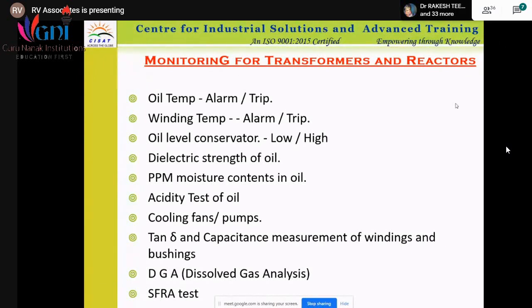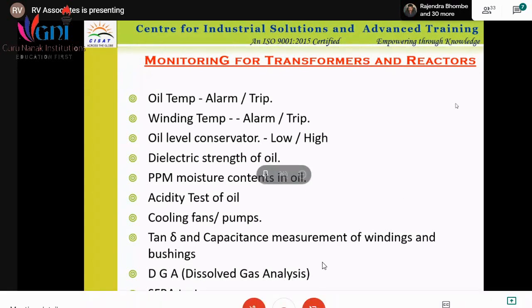Another parameter, the last third one, is the tan delta or capacitance measurement of winding and bushings. Please note that this tan delta and capacitance measurement has to be done wherever we are using insulation. It can be for cable, for motor, or for transformer. This gives you a direct indication of the healthiness of the system or the winding. Similarly, DGA, dissolved gas analysis, is an oil analysis. If there is a fault in the system and you check the oil, depending on the temperature rise, a number of gases are formed. Those gases are checked while testing the oil, and you get to know the exact reason.